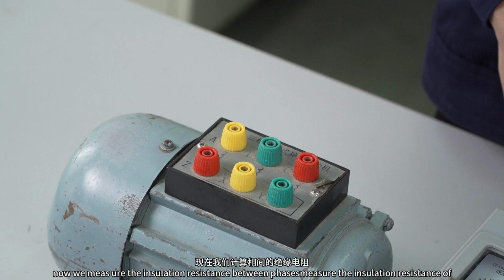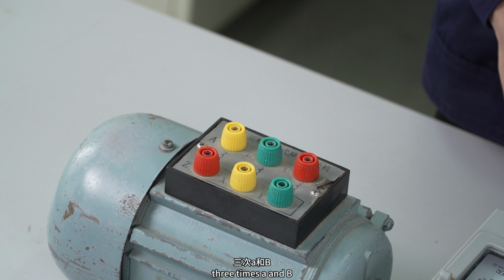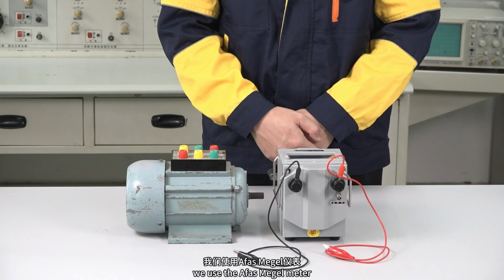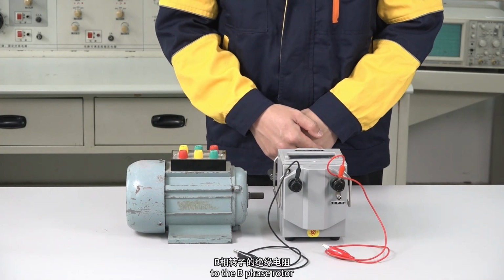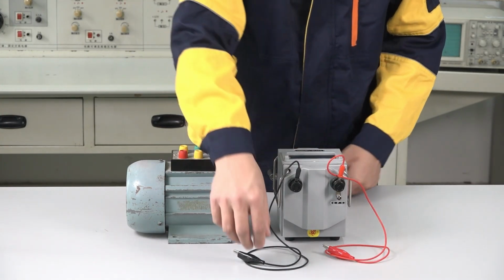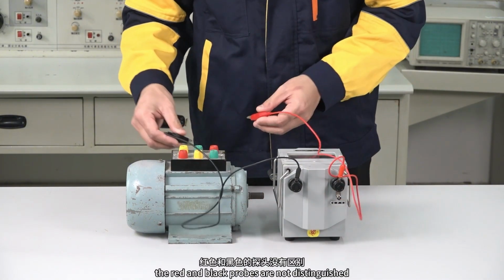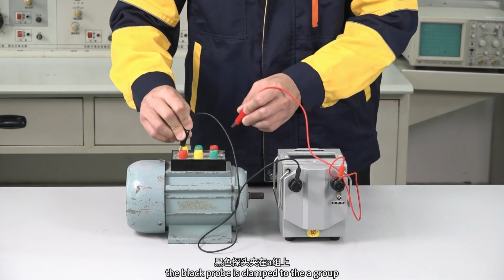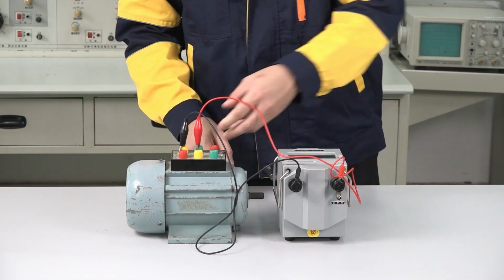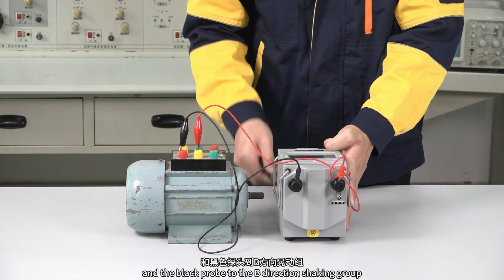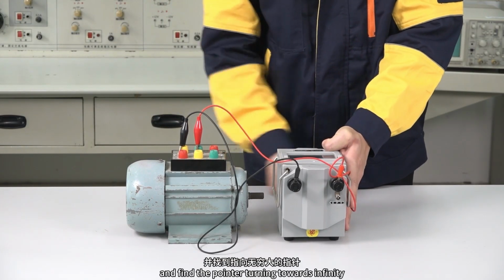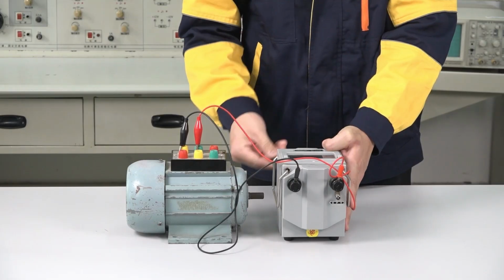Second, now we measure the insulation resistance between phases, the insulation resistance between A and B, A and C, and B and C. We use the megohmmeter on the motor. When measuring, the red and black probes are not distinguished. The black probe is clamped to the A phase group, and the red probe to the B phase group. Turn the handle, and we find the pointer turning towards infinity.